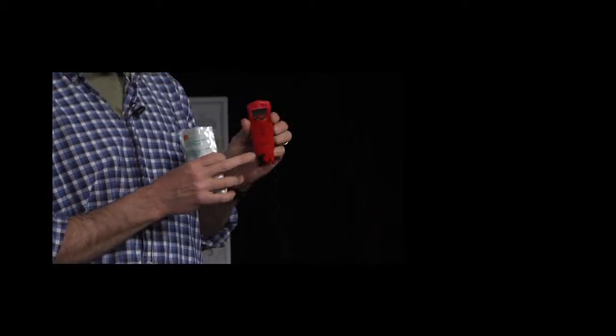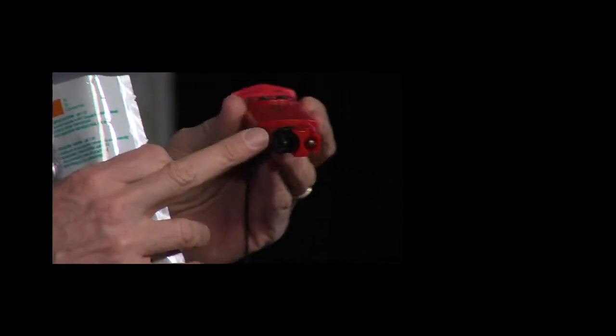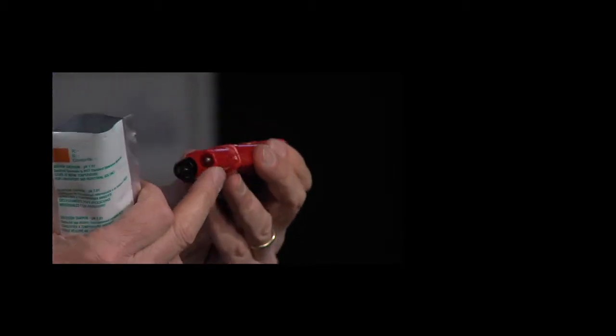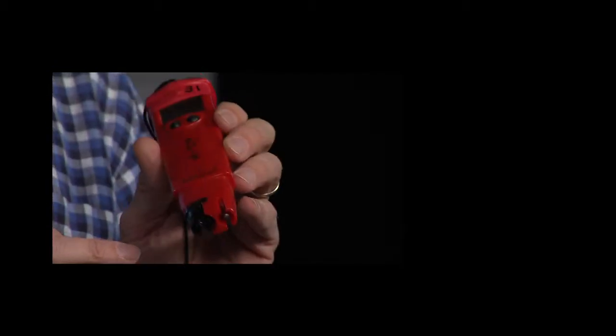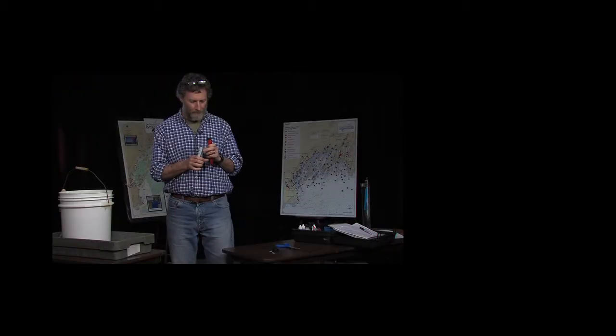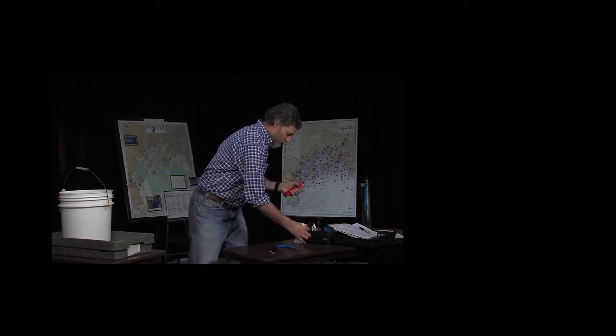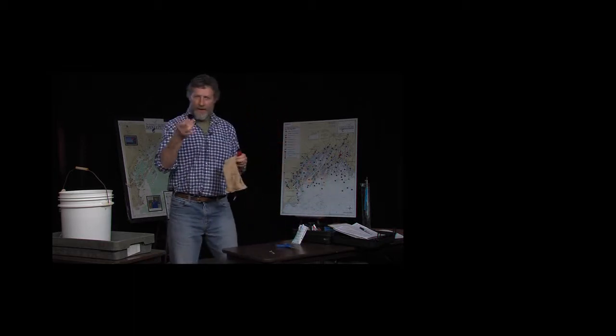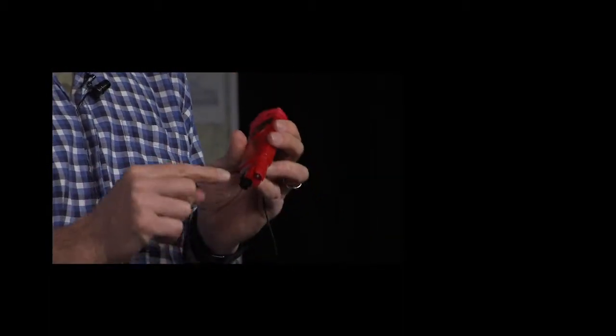And on the meter there are two sensors. There's a black sensor here that has a glass probe in the middle that actually measures the pH. The other sensor that's guarded here is a little shiny one that is a temperature thermistor. And the temperature thermistor will actually record the water temperature. And so this meter does water temperature and pH at the same time. The black cap that covered the probes has a small sponge inside, and the idea is to keep the probe wet at all times so that it works properly.